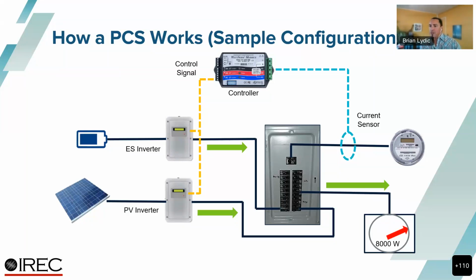In the lower right corner, you can see there are currently 8,000 watts of loads here. Let's say a large load like a clothes dryer turns off, dropping the power to 4,000 watts, just like that. That introduces inadvertent export, as the energy storage and PV inverters continue to produce the same power for a moment that they did before, but less of that power is now fed to the loads.